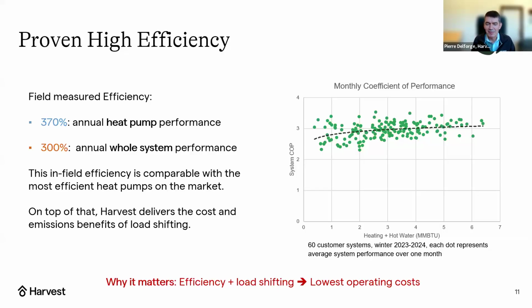So one of the questions that came up in the beginning of the webinar is, are there any compromises in getting a combi in terms of efficiency and cost? I think by now you probably heard that, from a cost saving, probably not, but from an efficiency standpoint, what we've proven, and we have field data and third-party verified data to prove it, is that we can operate the combi system at very high efficiency, on par with the highest efficiency heat pumps on the market. This data shows annual whole system performance around 3.0 COP, that's 300% efficiency, and heat pump efficiency at 370% average. And this is accounting for the real world, not just the COP number in the lab. It accounts for defrost, for people leaving doors and windows open, electric resistance coming in if needed. So this is on par with the very highest efficiency heat pumps you'll find in the market.